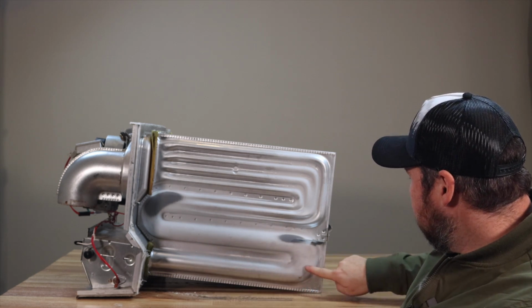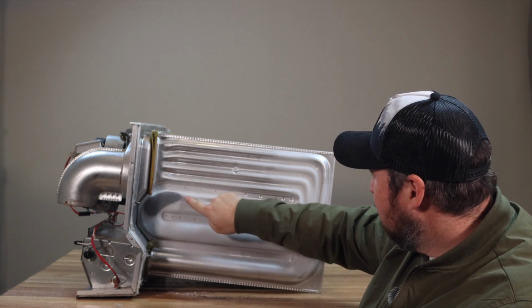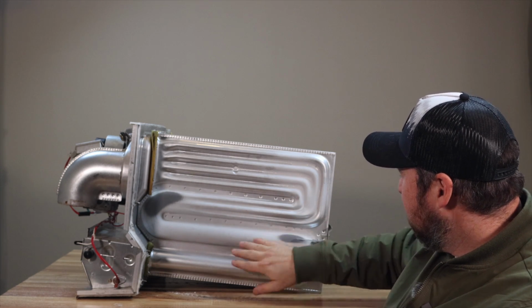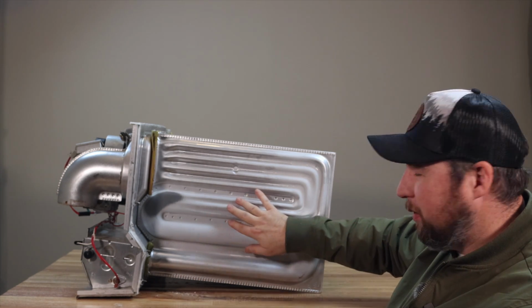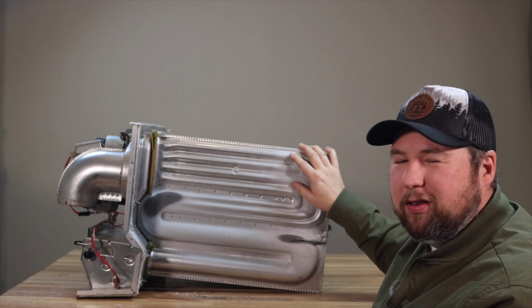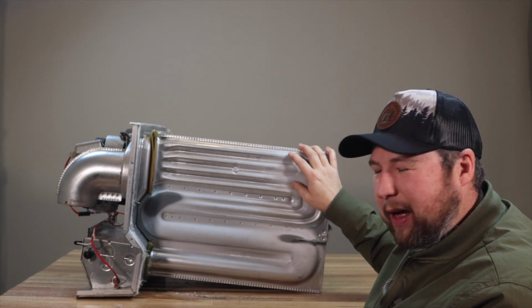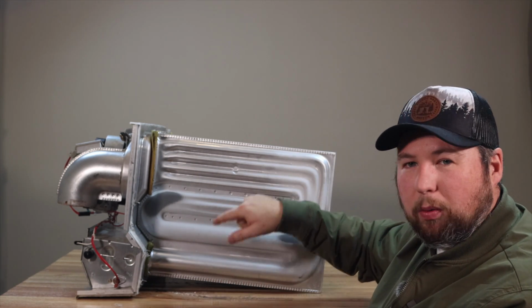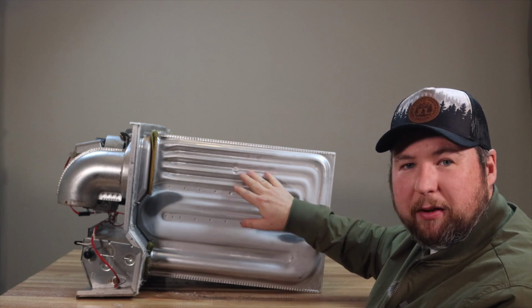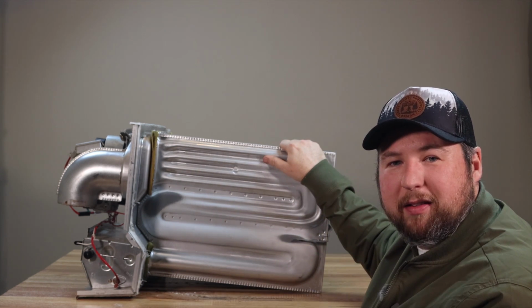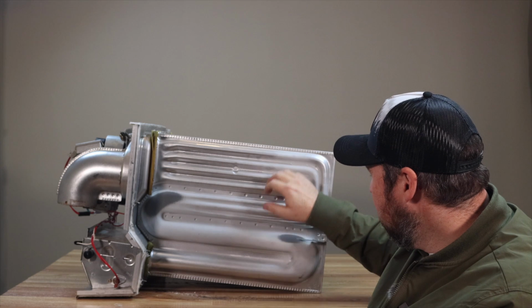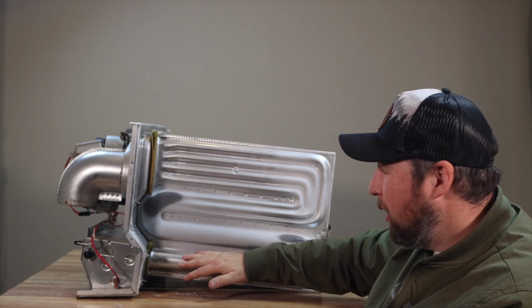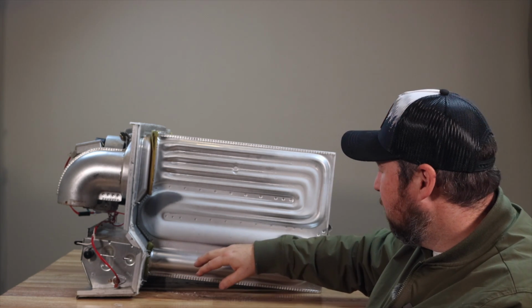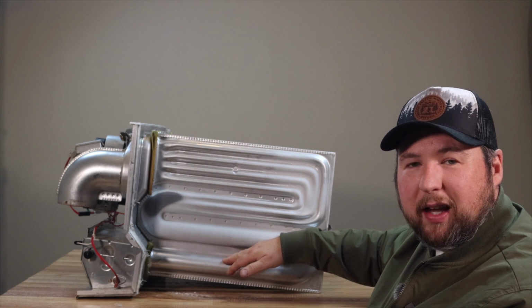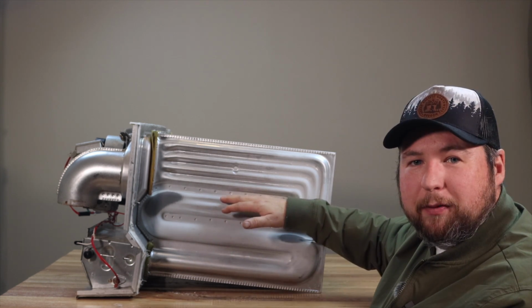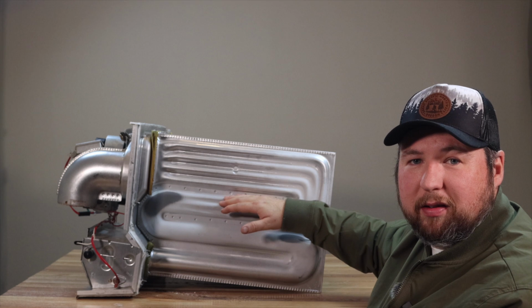And then it's going to make a big U-turn here, and then another U-turn, and then another U-turn. Now you can see here that this one starts off as one tube and it splits off into three. That's just an efficiency thing. Not all of them do that. Some of them will just be straight one tube the whole way. But different manufacturers are trying to maximize the amount of heat transfer as possible. So what ends up happening is near the bottom, where the blower is, it's going to be below this. It's going to absorb the most heat into the air. So by the time you're getting up to the top, you've lost quite a bit of heat, and that's just because it's going into the air.